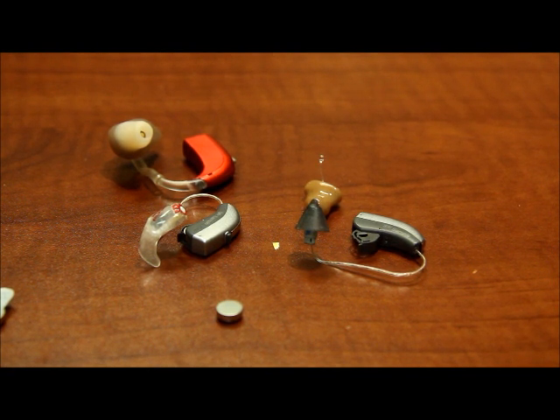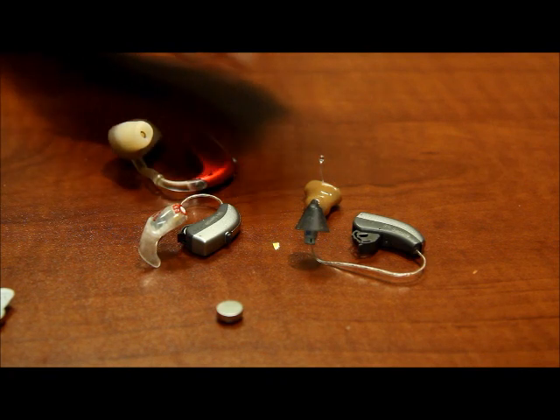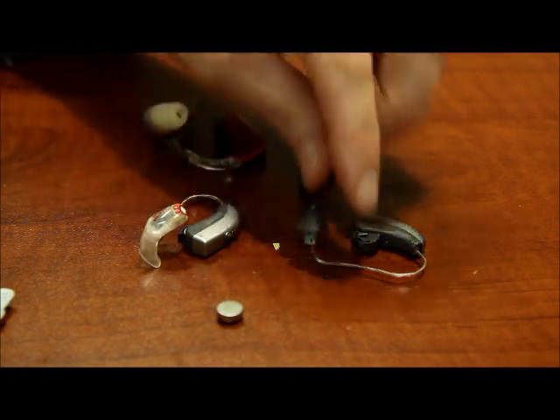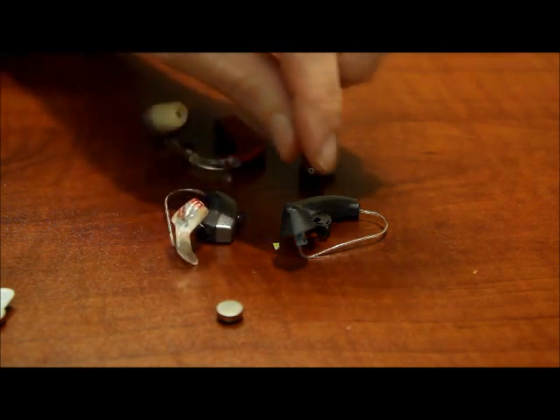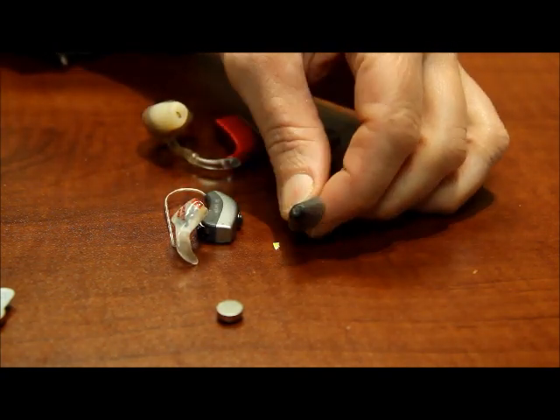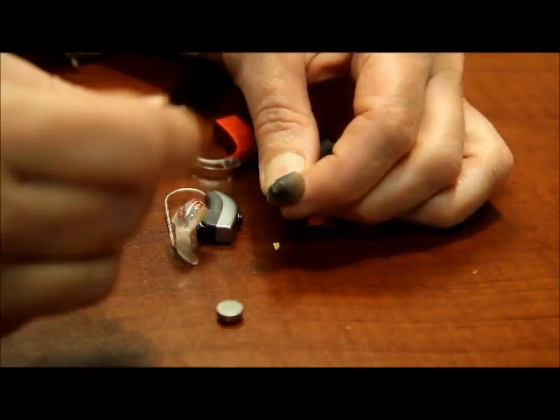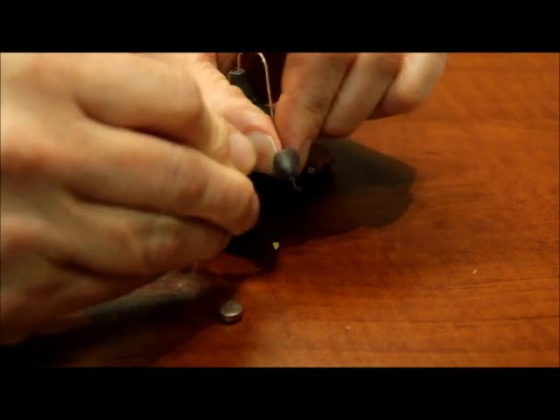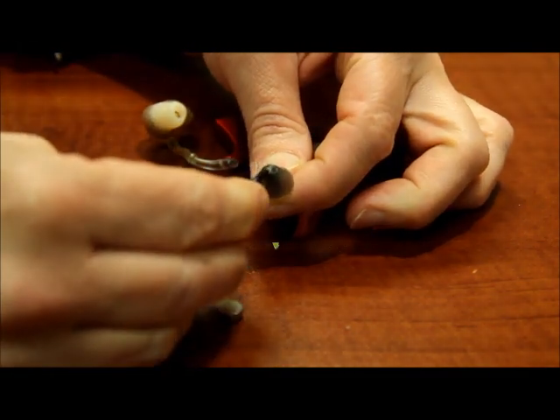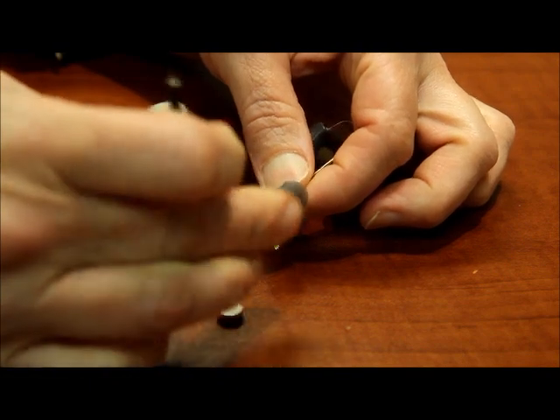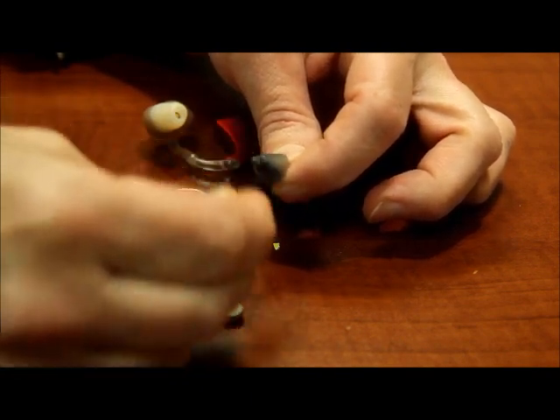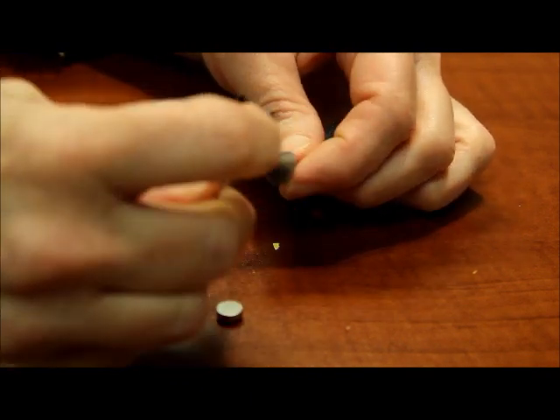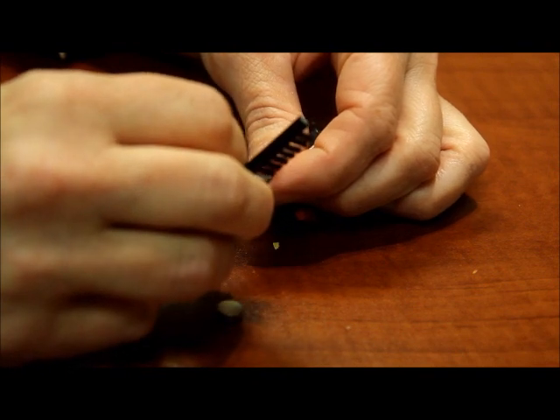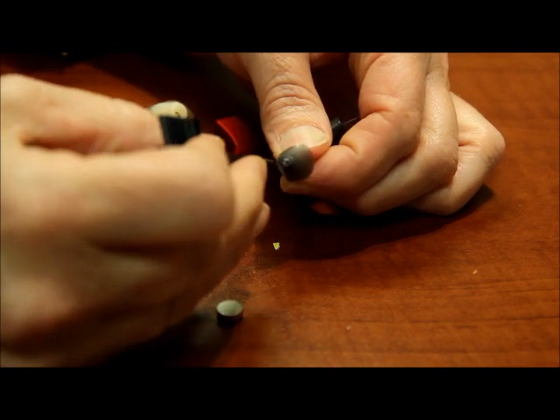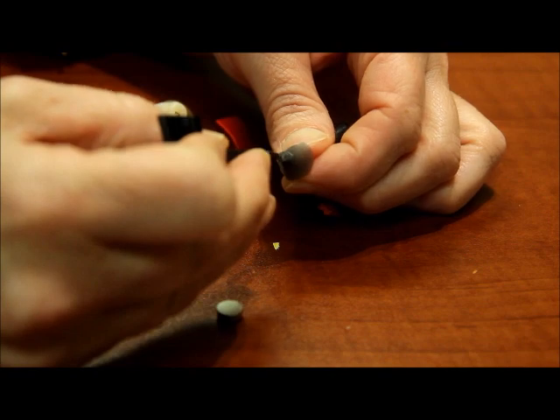Okay, so if you have a receiver in the ear hearing aid and use a silicone dome, it is possible that the openings on the dome itself can become clogged, giving the same perception that the hearing aid has stopped working. There you see it's a little, in this case it's a gray dome. There is an opening on the end, and that opening can be clogged with wax or other debris, and you might think that the hearing aid's not working, or it might not be working as well. It's something to check out.